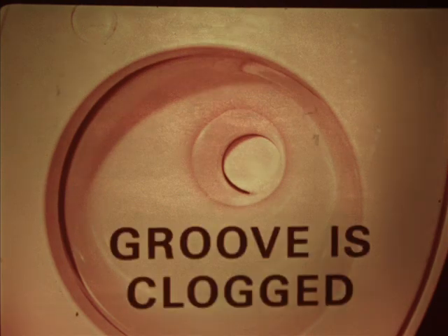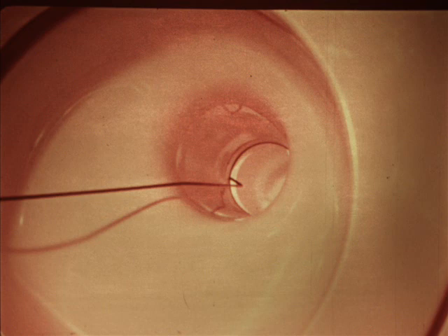If the blade is not closing, it is probably because the groove into which it seats when completely closed is clogged with foreign material. The solution or repair is simple. Insert the end of a coat hanger or similar object into the sealing groove and remove the foreign material. Avoid damaging the rubber seal while cleaning.